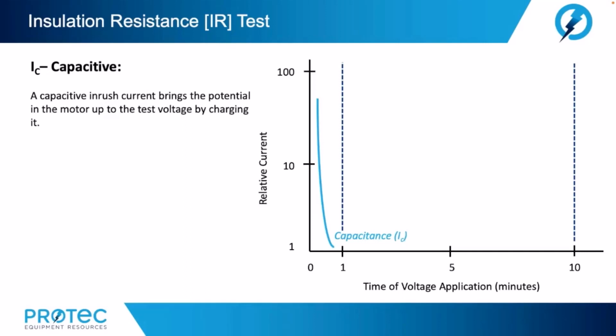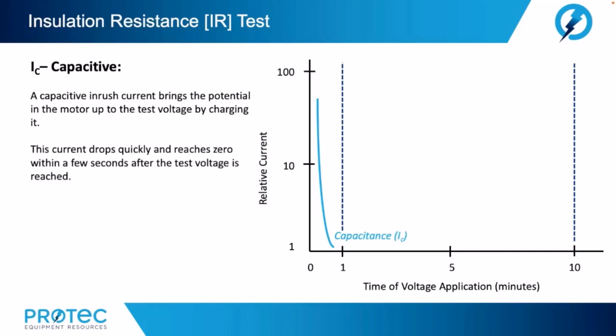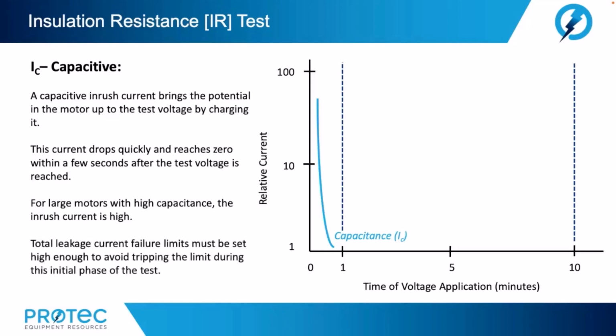A capacitive inrush current brings the potential in the motor up to the test voltage by charging it. This current drops quickly and reaches zero within a few seconds after the test voltage is reached. For large motors with high capacitance, the inrush current is high. Total leakage current failure limits must be set high enough to avoid tripping the limit during this initial phase of the test.